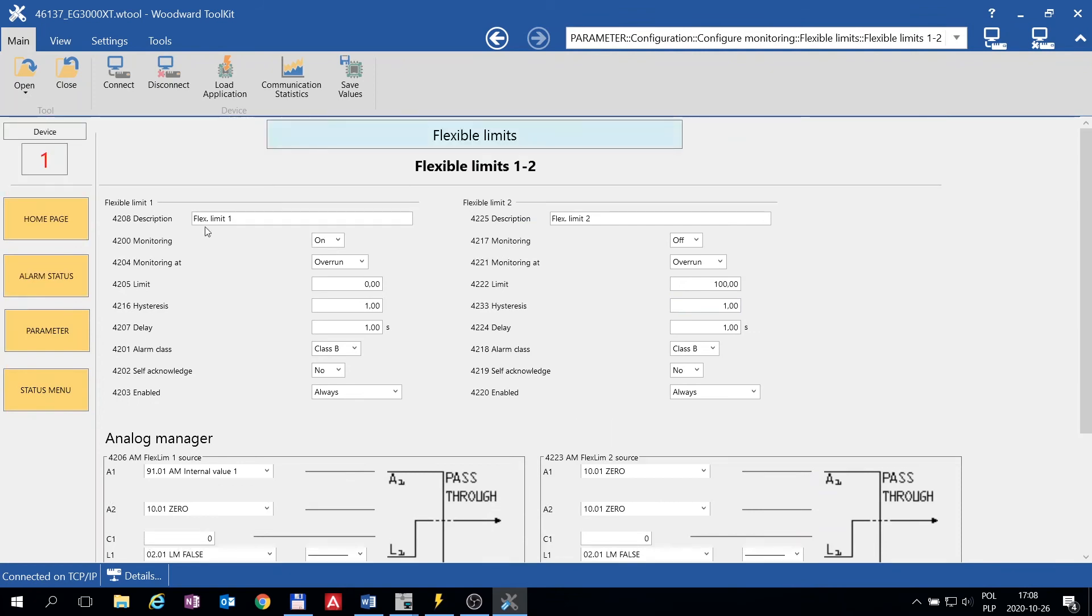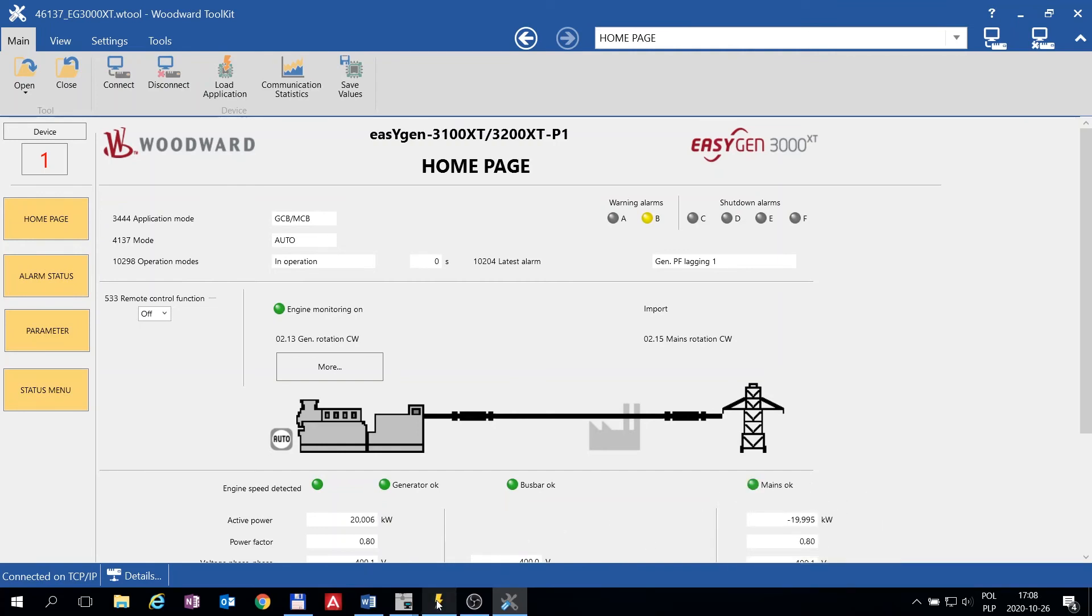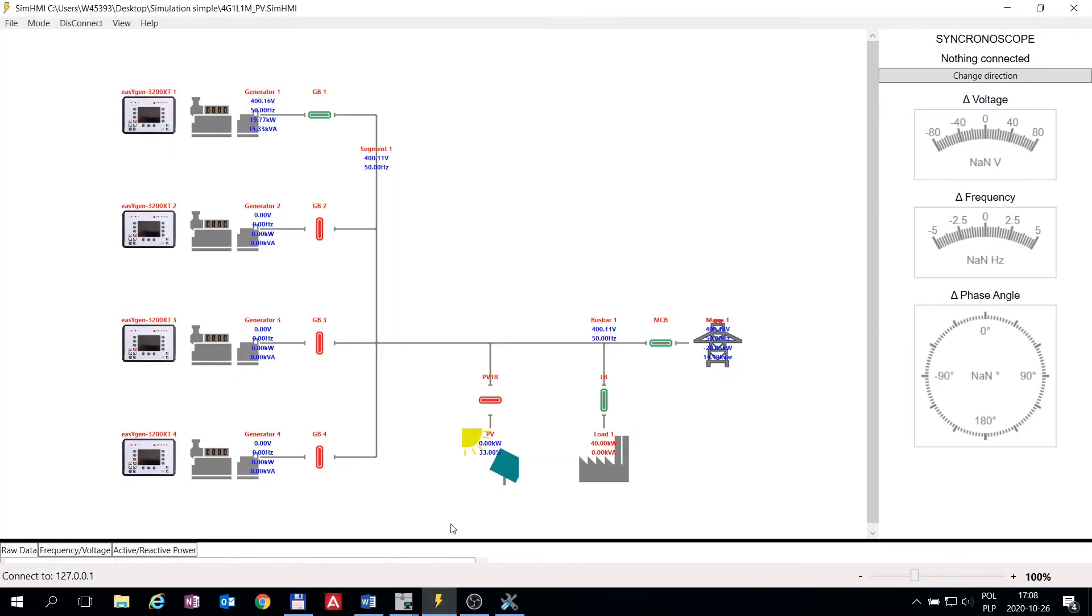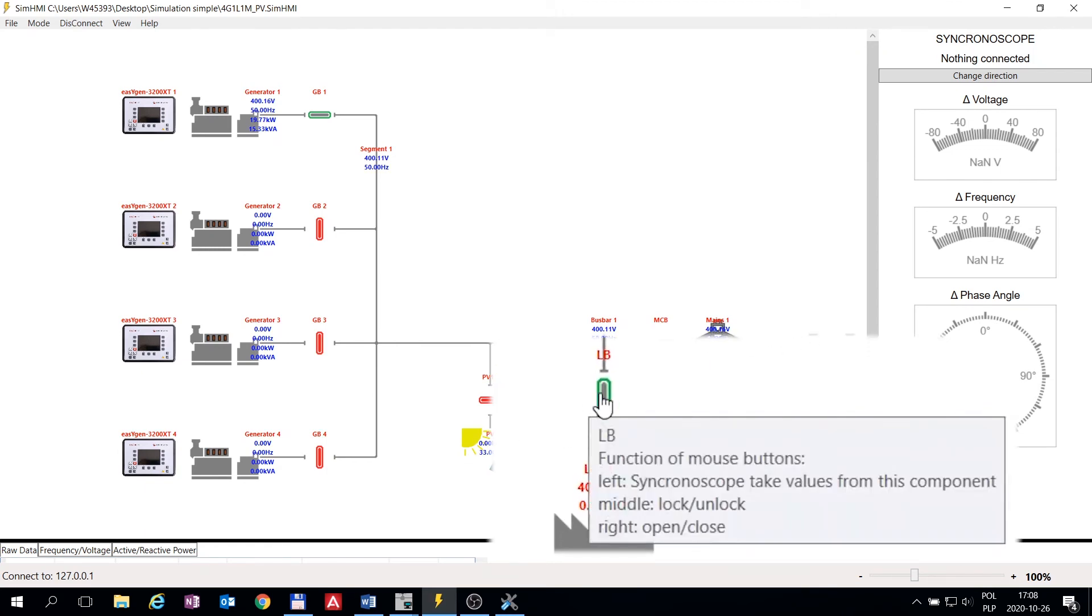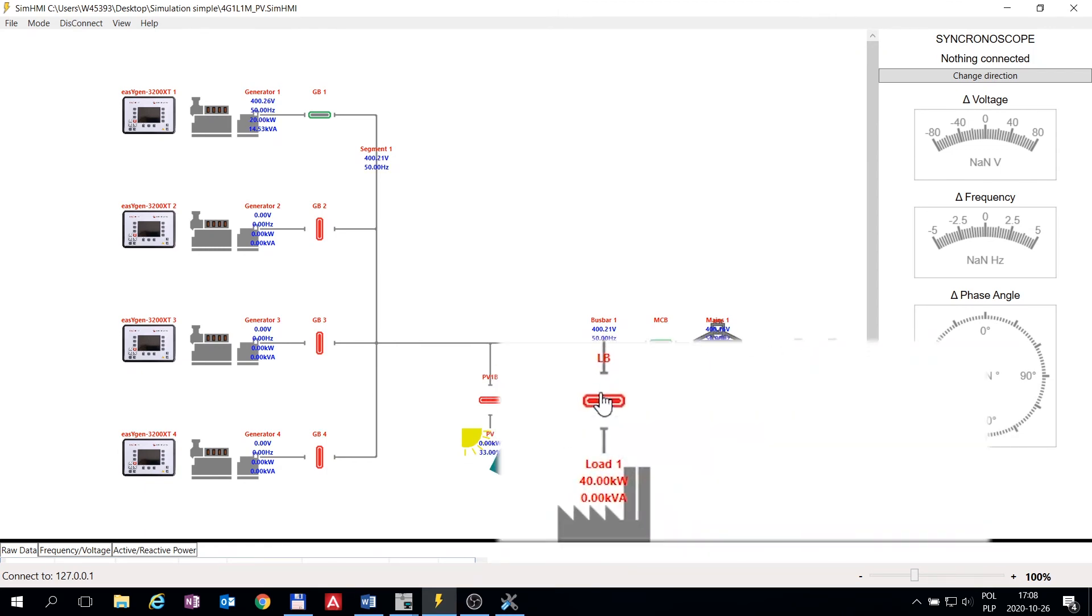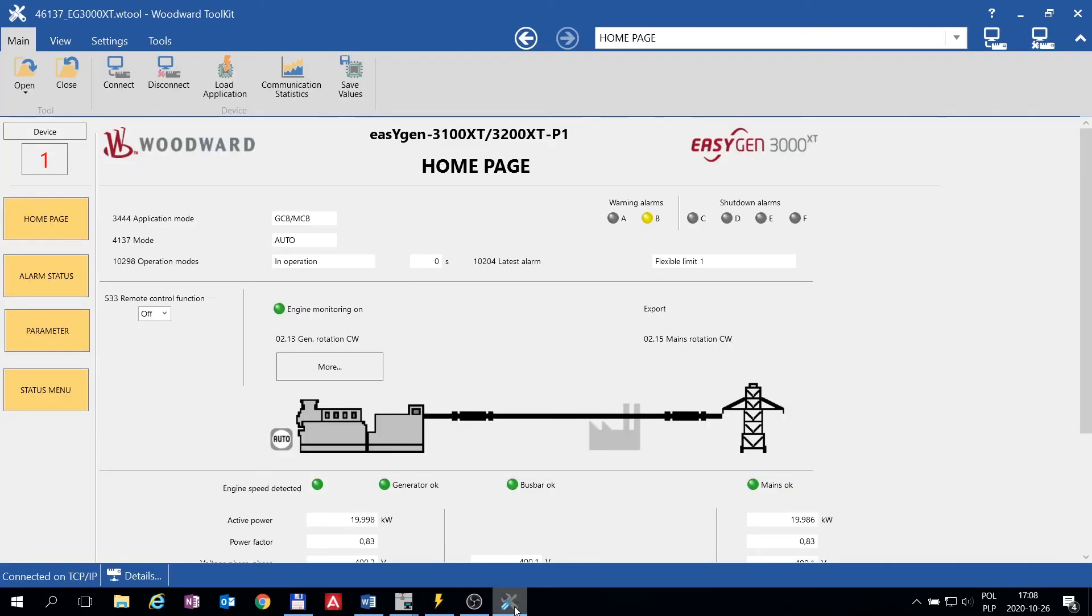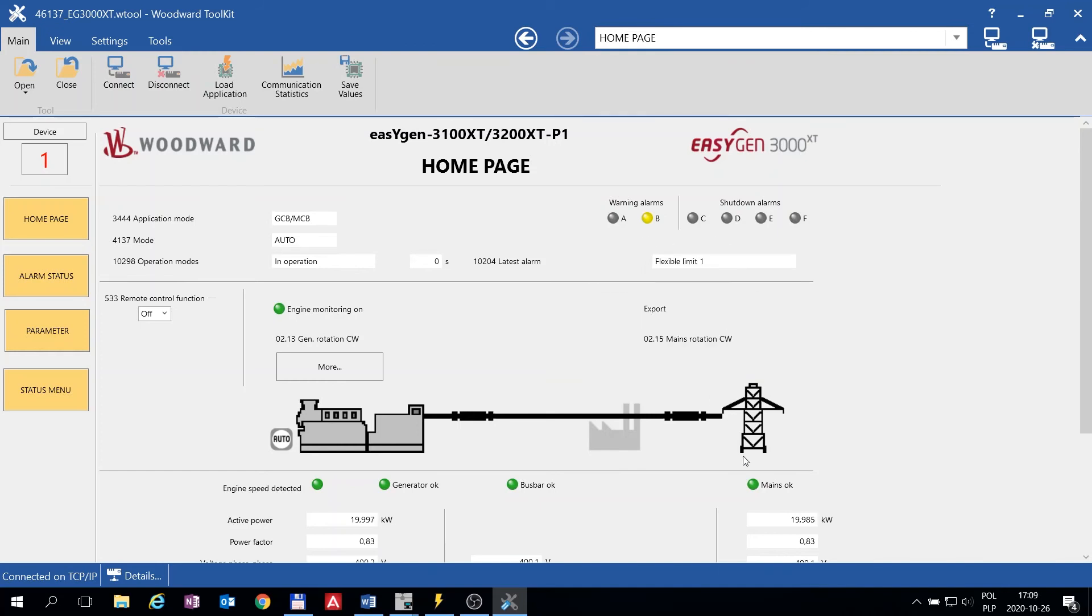Now I am going to simulate a power export situation by disconnecting the load. Here you can see we are still importing some power. Now I will open Load Breaker. This, as you can see, initiated our Flexible Limit because for some moment we were exporting power to the grid.